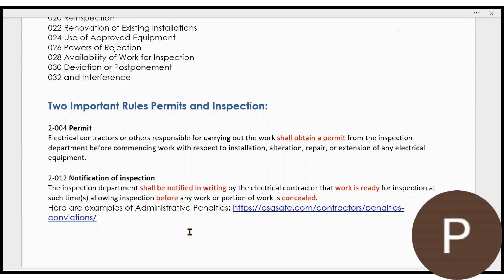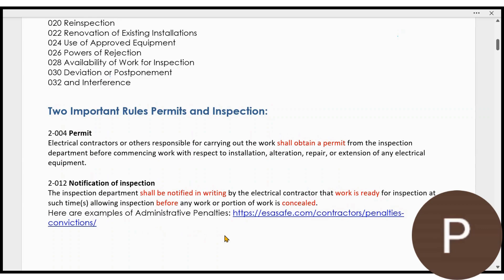The second rule is notification of inspection. The inspection department shall be notified in writing by you, the electrical contractor, that the work is ready for inspection so that the inspection can be performed before that work is concealed. You don't do the work, pull the permit, do the work, put up drywall, and then ask for it to be inspected. It has to be inspected before it is concealed.